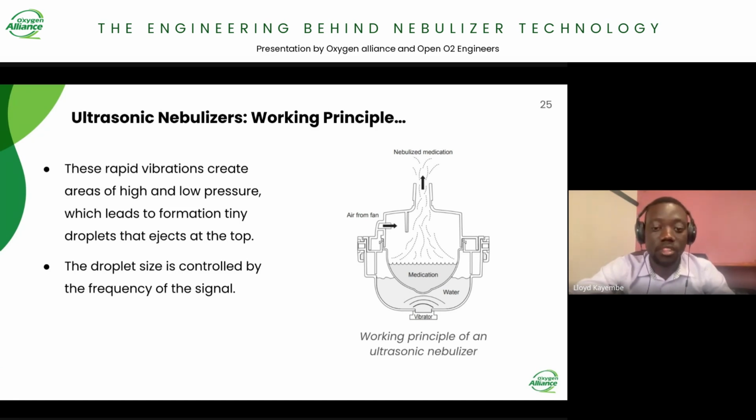These areas of high and low pressure cause cavitation within the medication, meaning that tiny bubbles are formed within the medication.